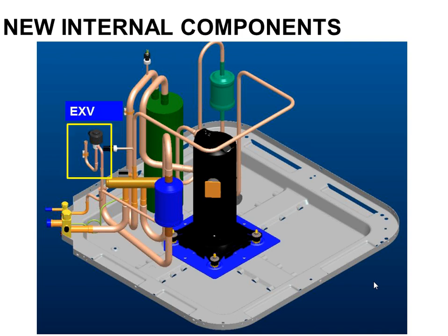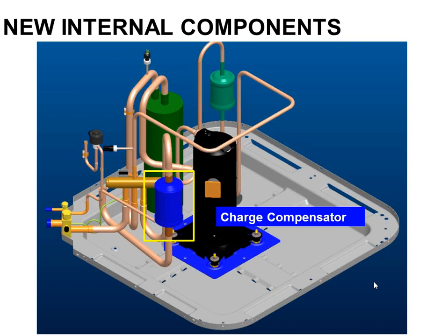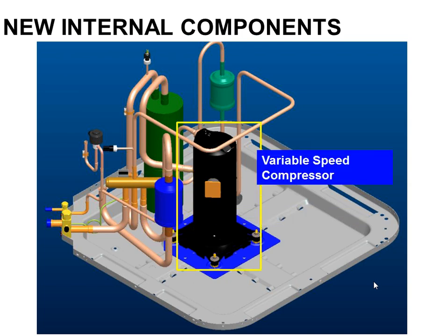Some of these components inside the unit, if you took the coil off them and looked in there, there's the EXV. I'll show you a picture of that in a minute. That's a 600-step EXV used to position refrigerant flow going into the unit. There's that charge compensator. Well, actually, that might be the external muffler. The charge compensator is probably the green one in the back. I think the wrong box is circled there. Probably that big green one is the charge compensator, and the blue one is the external muffler.